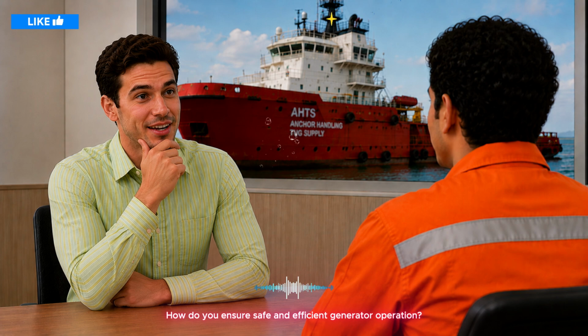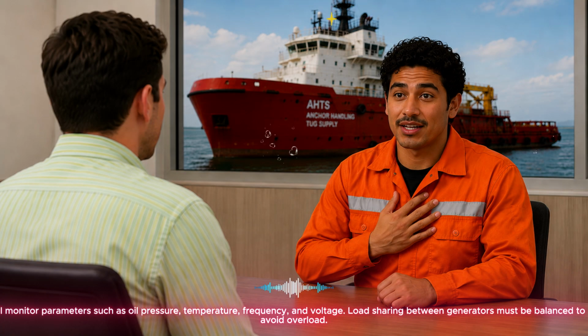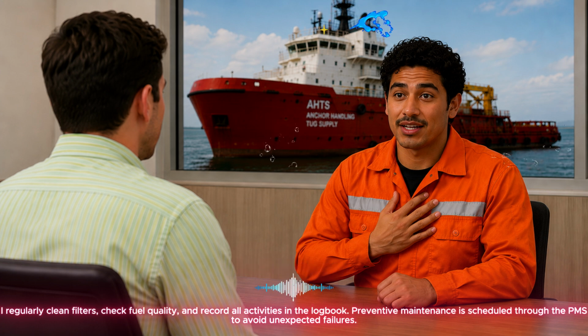How do you ensure safe and efficient generator operation? I monitor parameters such as oil pressure, temperature, frequency, and voltage. Load sharing between generators must be balanced to avoid overload. I regularly clean filters, check fuel quality, and record all activities in the logbook. Preventive maintenance is scheduled through the PMS to avoid unexpected failures.